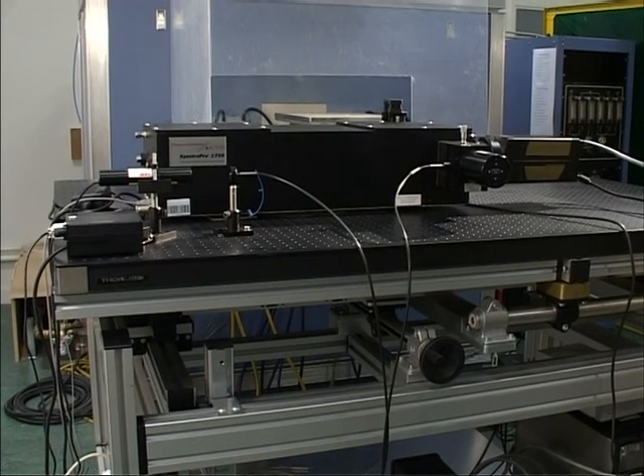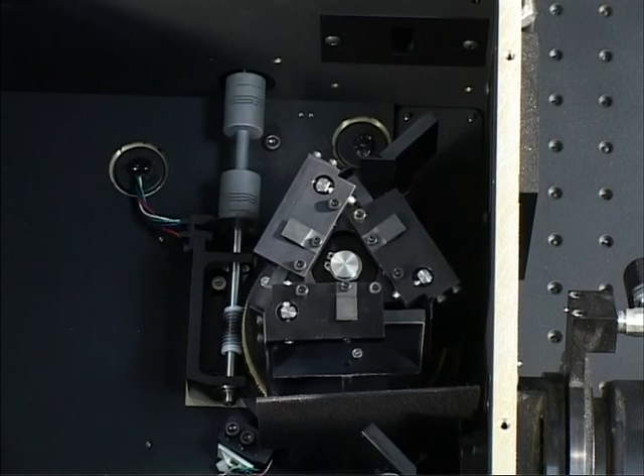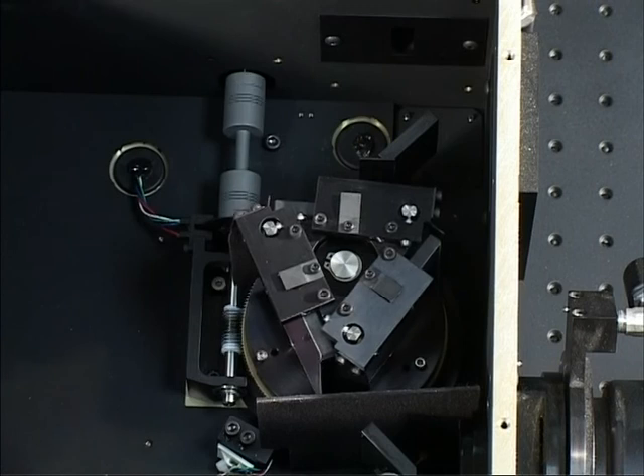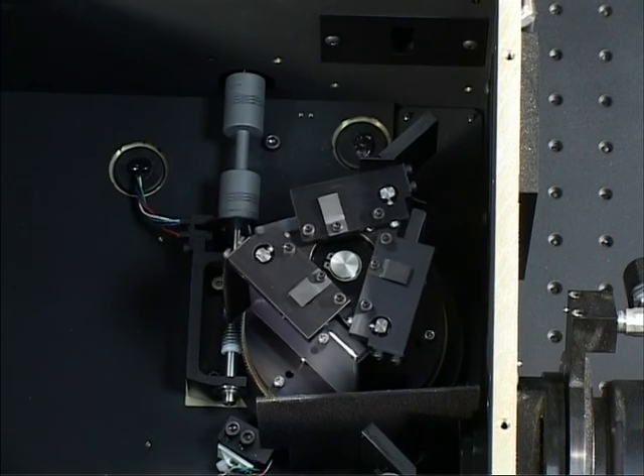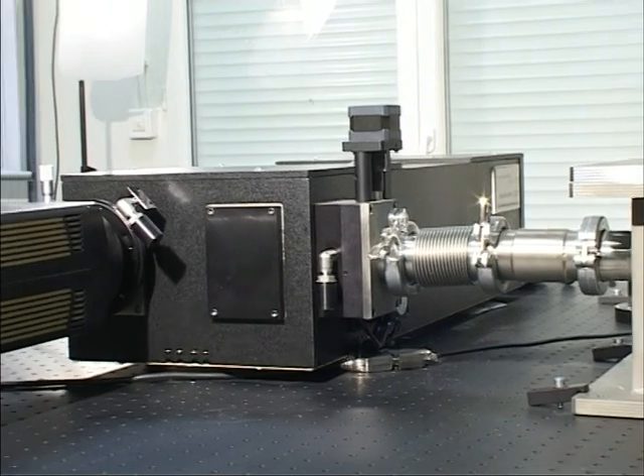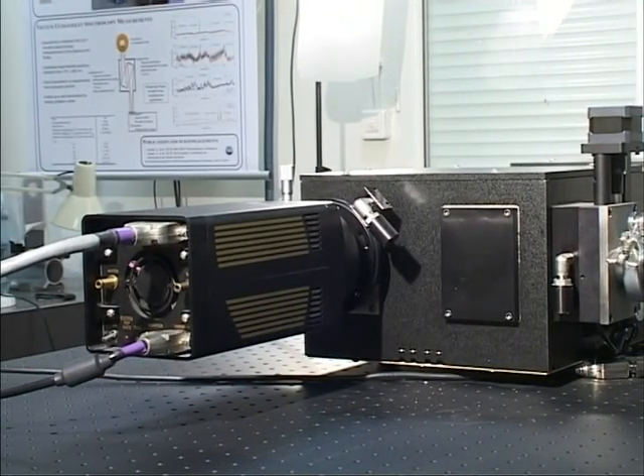This high resolution spectrometer has a focal length of 75 centimeters and can be equipped with nine interchangeable gratings covering the entire spectral range from the vacuum ultraviolet at 150 nanometers to the mid-infrared at 6 microns. The spectrometer is also equipped with a VUV enhanced CCD camera allowing measurements from as low as 150 nanometers.